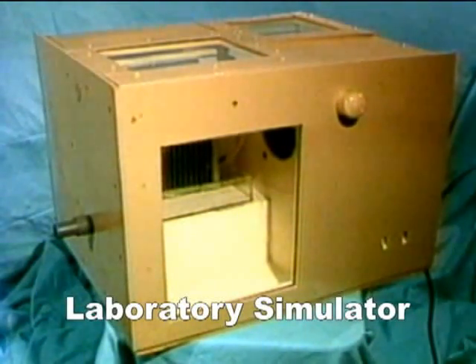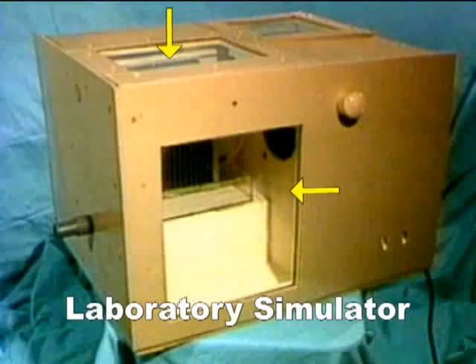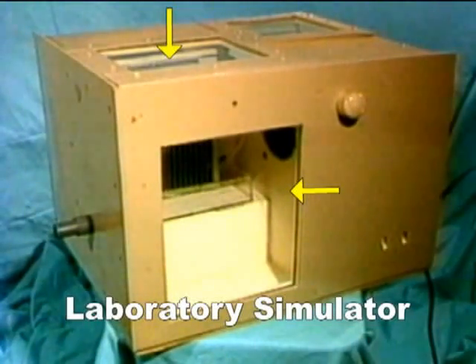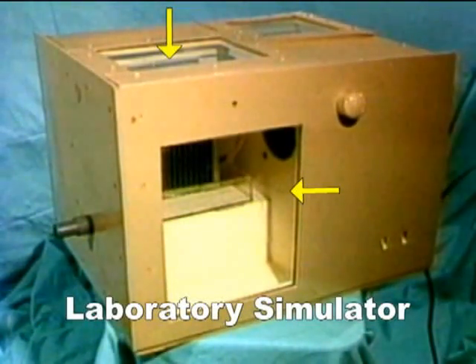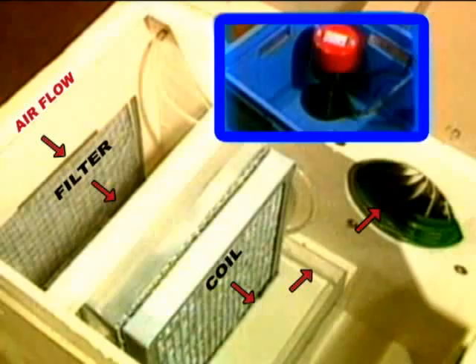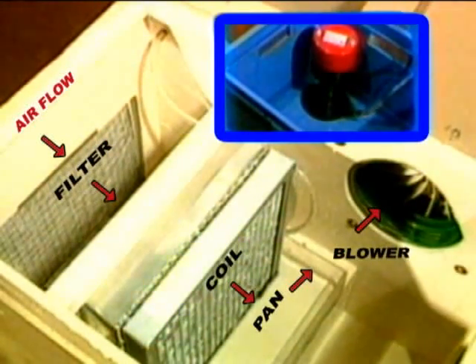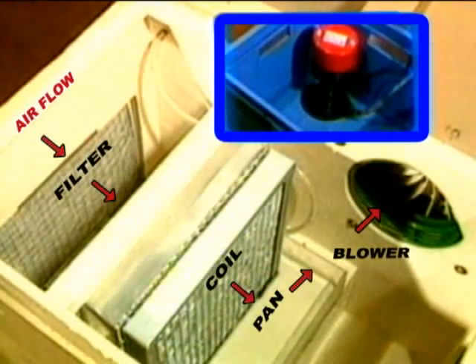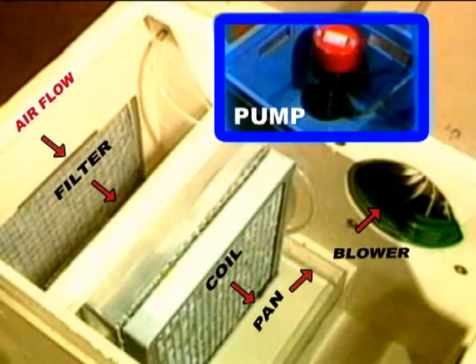The simulator is equipped with transparent panels to show what actually occurs inside the air handler of an air conditioning system — events that are not readily visible during system operation. Just as in a real air conditioner, air is drawn through the filter, the cooling coil, across the drain pan, and into the blower. For this demonstration, the blower airflow is set to create a partial vacuum in the drain pan compartment, which is typical of air conditioners.